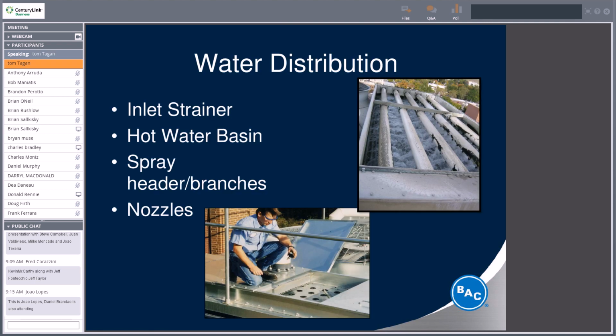Moving on, so here's those pages we just went through was the O&M manual that they asked them to insert. This is going to be kind of a recap of some of the things we've talked about. As you can see, the picture up on the right-hand side, that is a pressurized distribution system. That would be in your centrifugal fan towers typically. So there's spray nozzles there. Those PVC headers are all pressurized. So you can just see the even distribution over the fill. So if you pulled off your drift eliminators from the tower and looked down, this is what you saw. That's a pretty good indication that your nozzles are clean and you're getting a good distribution over your fill. Or your coil, if it happens to be. That actually looks like a coil product in a closed circuit cooling tower.